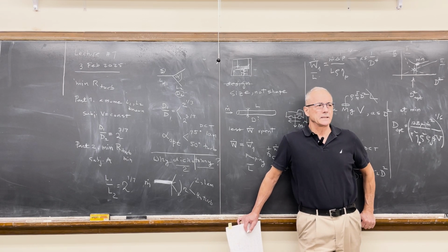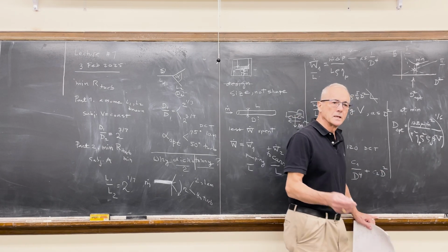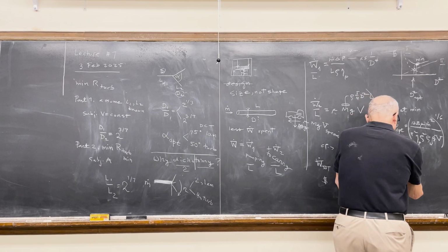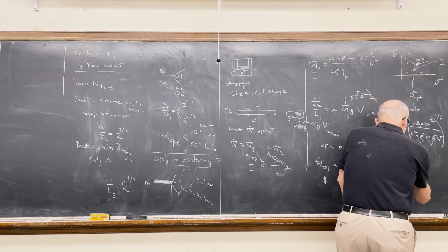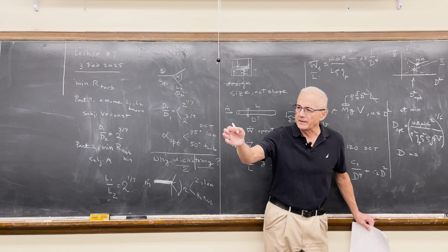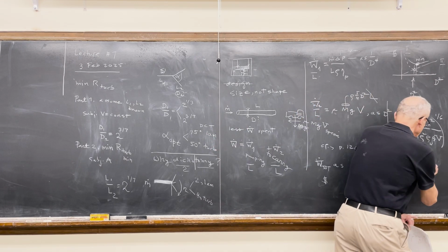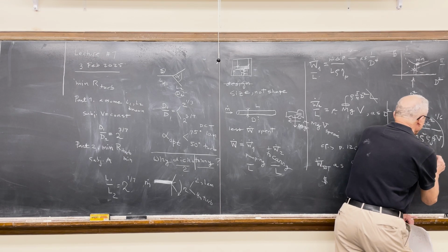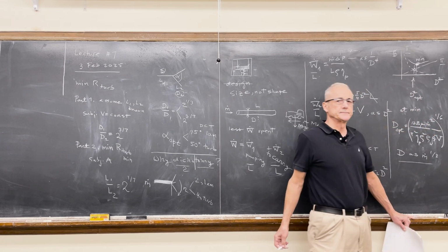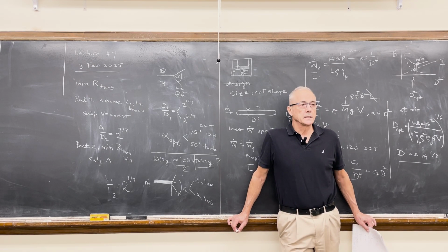But one easy way to remember this discovery is that you should expect duct diameters to vary in proportion with the mass flow rate to power 1/3. Predicted.